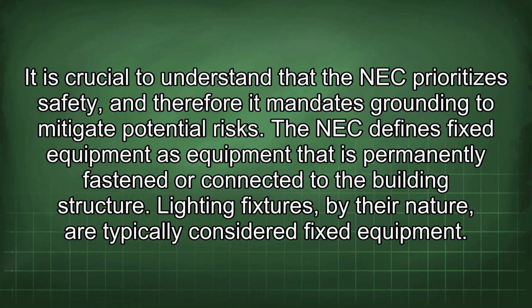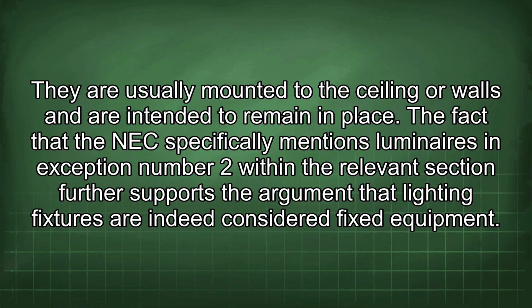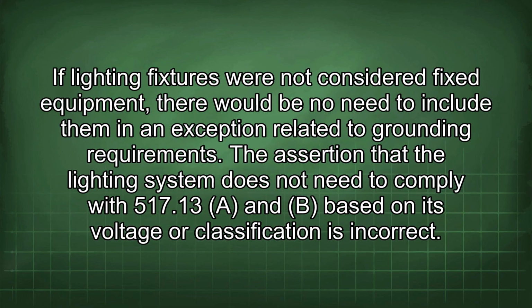mitigate potential risks. The NEC defines fixed equipment as equipment that is permanently fastened or connected to the building structure. Lighting fixtures, by their nature, are typically considered fixed equipment. They are usually mounted to the ceiling or walls and are intended to remain in place. The fact that the NEC specifically mentions luminaire as an exception number 2 within the relevant section further supports the argument that lighting fixtures are indeed considered fixed equipment.